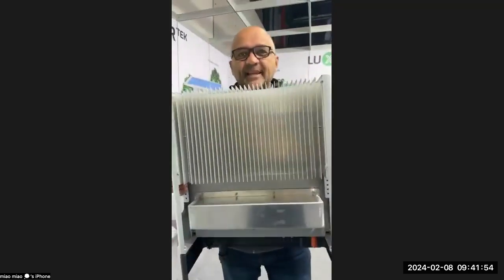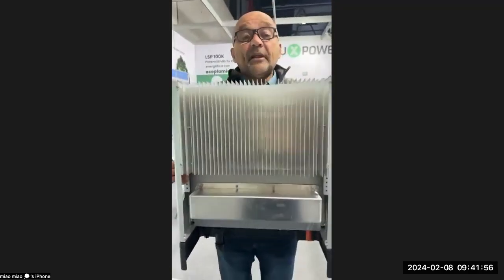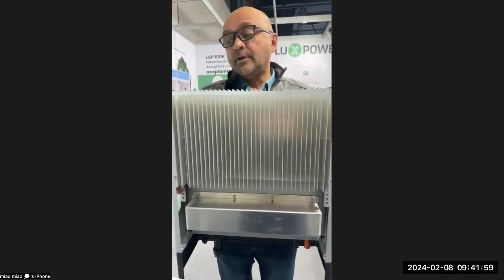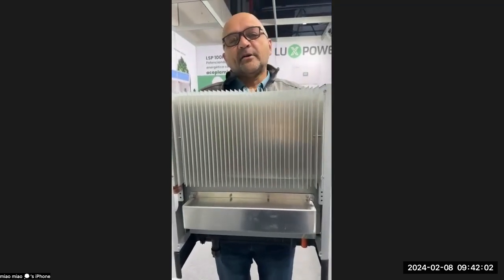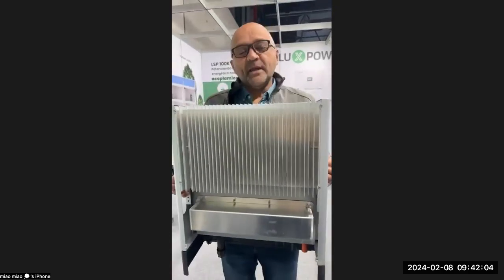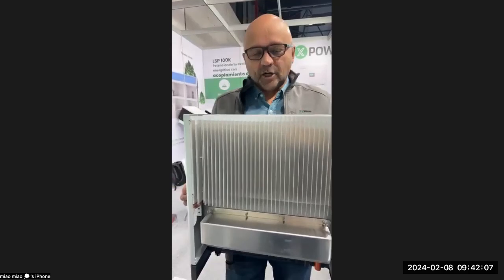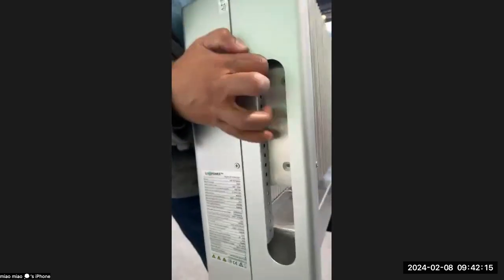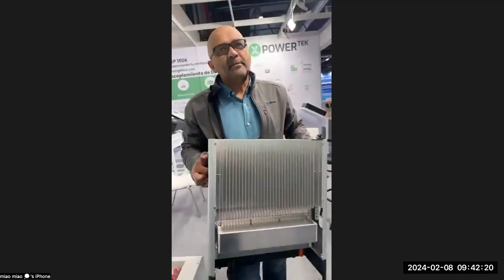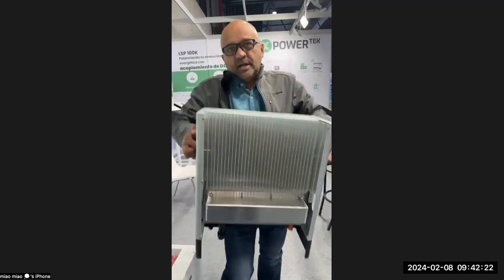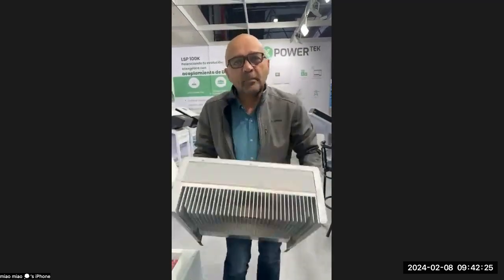It's quite a handy machine. I can see the heat sink. Yeah, you can see the heat sink. And the nice thing about the LXP5 is that it has no mounting holes in it, because inside the top tray there's a mounting bracket. You simply mount the bracket on the wall. It has hooks that go through the fins here and hang on those two bolts there. On one side you have a locking bolt, a single tapered Allen screw, so that once the machine is on the wall, you simply put the locking bolt in and it can't be knocked off by accident.